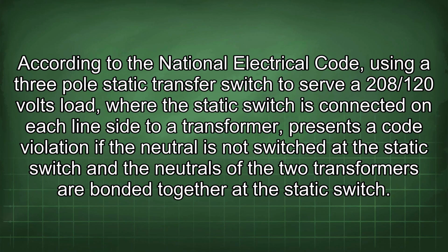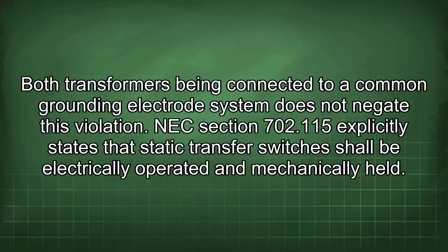According to the National Electrical Code, using a 3-pole static transfer switch to serve a 208/120 volts load, where the static switch is connected on each line side to a transformer, presents a code violation if the neutral is not switched at the static switch and the neutrals of the two transformers are bonded together at the static switch. Both transformers being connected to a common grounding electrode system does not negate this violation.